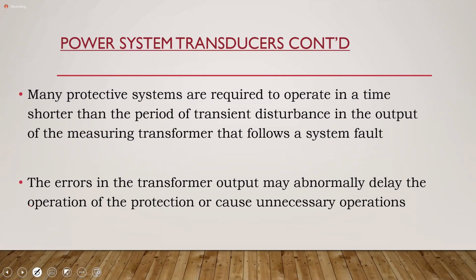Yes, sir. So there are certain strictures that are applied to your CTs, right? In terms of the errors that are associated. And as I said earlier, there are certain classifications that we will apply to our CTs. So you can't just walk in and say, well, I have this level of current that I'm monitoring and I want a CT to do it. No, there's a lot more information that needs to be provided. Albeit, I tell you upfront that most of the equipment that you'll be interfacing with, whether it be your transformers, your power transformers, they come with their CTs built in, all right?